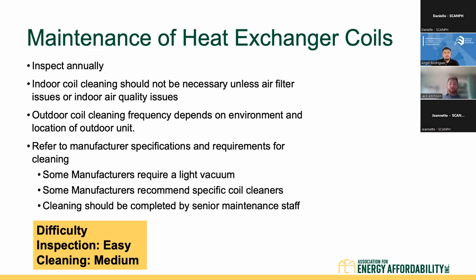If you have to clean your coil, you should refer to manufacturer specifications and requirements for cleaning. Some manufacturers only allow a light vacuum on the coil to remove dust and debris. Some manufacturers recommend specific coil cleaners that are able to remove all of that dust and gunk off the coil. Cleaning should be completed by senior maintenance staff. It does require taking apart the equipment, and it requires someone knowledgeable about the equipment, so we don't accidentally break the equipment when we're trying to maintain it. So it should be done by a senior maintenance staff person.